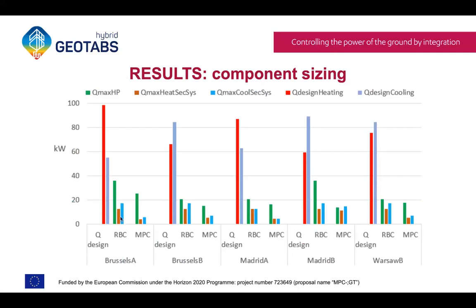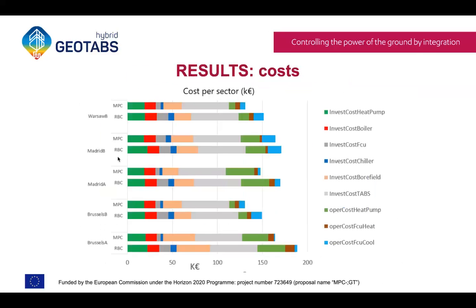What is interesting to see is that compared to a steady state design situation, we typically find a total design power of the combined system that is substantially lower than the steady state design. Since the hybridGEOTABS system is a very investment-intensive type of system, and the main cost is in the investment, reducing the design sizing has a big impact on the total cost of ownership of the system.